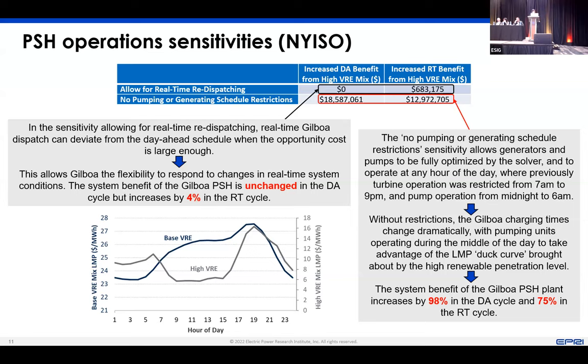And then the last sensitivity I want to highlight here, I've got it in red because I think it's a really important one. We're calling it no pumping or generating schedule restrictions. So if you remember at the very start, I talked about the extra constraints we had on the New York pump storage plant versus the Duke pump storage plant. And one of those was limitations in terms of when it could pump versus generate. And so if we remove that now, the Gilboa charging times change dramatically. So instead of pumping in the middle of the night, it now pumps during the middle of the day because it's taking advantage of that duck curve that occurs in high renewable scenarios. And so the system benefit actually increased very substantially, almost by a factor of 2 in the day-ahead cycle and very substantially in the real-time cycle. So what that tells us is it's really important for us to revisit these operating assumptions that we have baked into our systems as we transition to different systems.